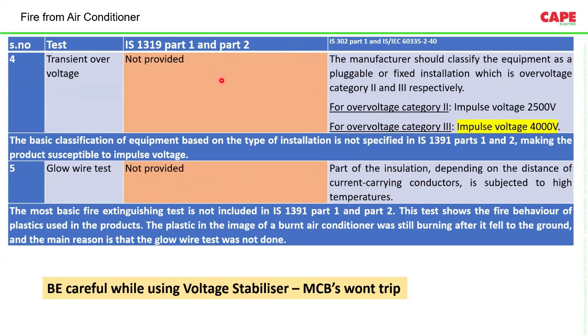Please be careful. 70% of the fires in hospitals are from air conditioners, especially these window or split air conditioners. So ensure that the new air conditioner you are buying has the ISI mark and, in addition, is tested as per IS 302. All the electrical parameters are tested. And when you install it, be very careful about the voltage stabilizer. If you use a voltage stabilizer, instantaneous tripping of MCBs may not happen. During a short circuit, the MCBs may not trip instantaneously.